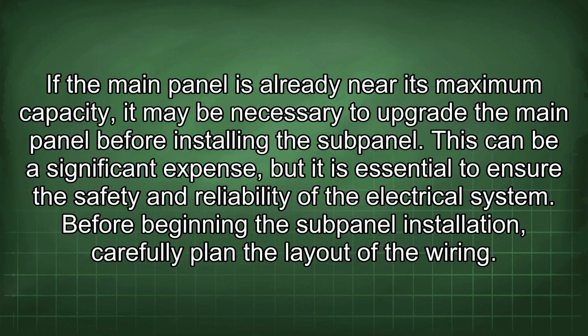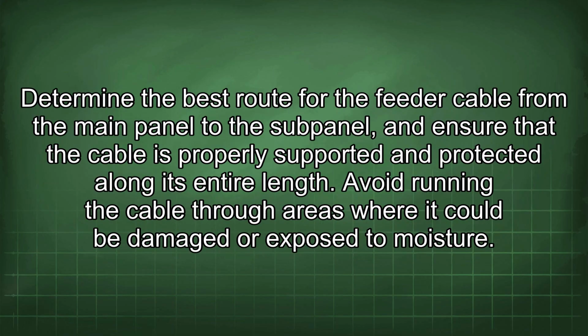Before beginning the subpanel installation, carefully plan the layout of the wiring. Determine the best route for the feeder cable from the main panel to the subpanel and ensure that the cable is properly supported and protected along its entire length. Avoid running the cable through areas where it could be damaged or exposed to moisture.